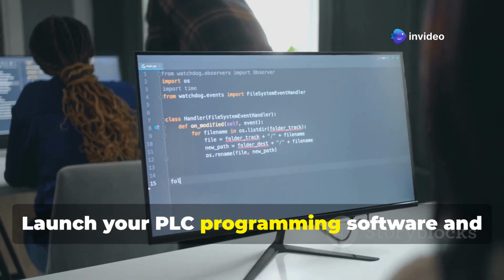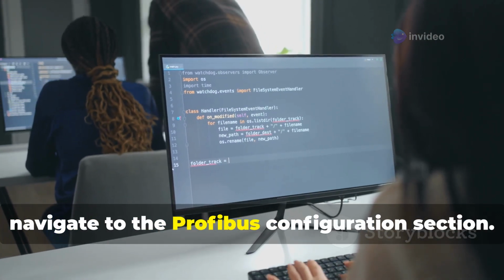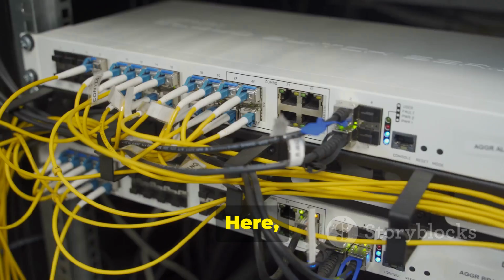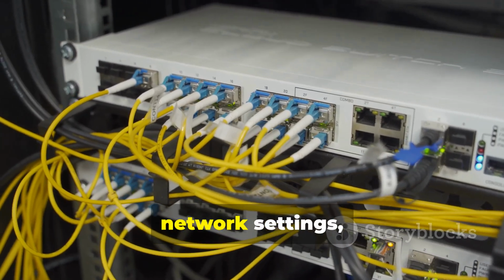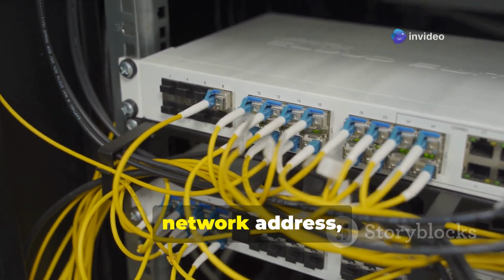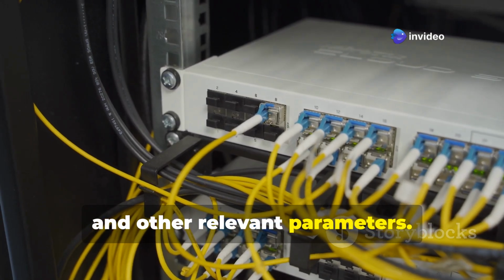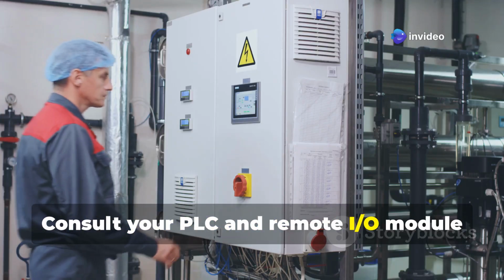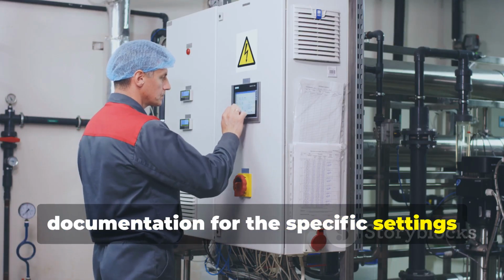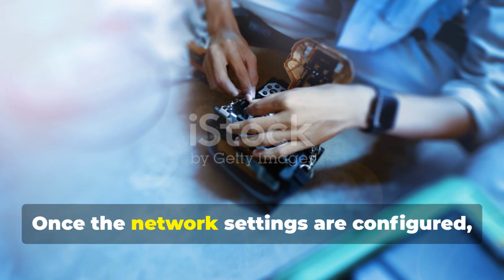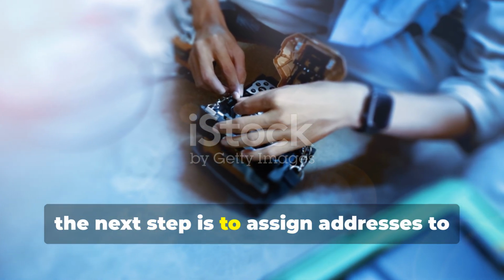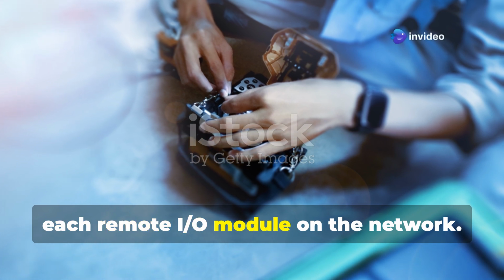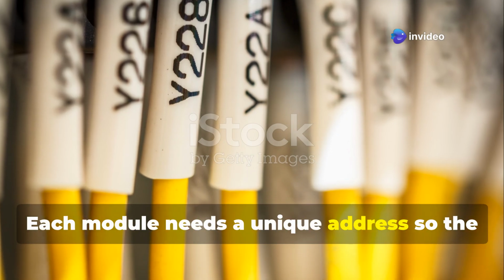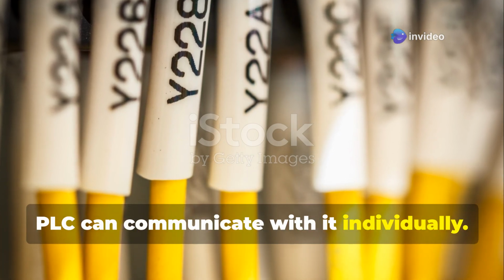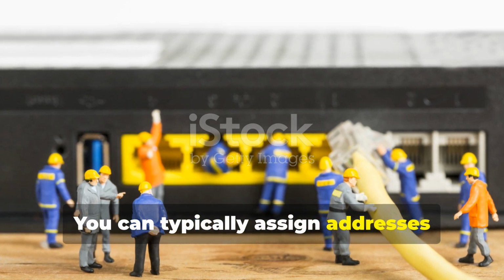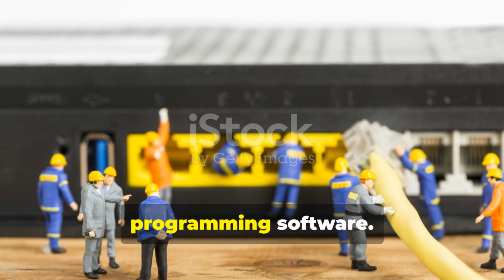Launch your PLC programming software and navigate to the Profibus configuration section. Here you will need to configure the Profibus network settings, including the baud rate, network address, and other relevant parameters. Consult your PLC and remote I/O module documentation for the specific settings required for your setup. Once the network settings are configured, the next step is to assign addresses to each remote I/O module on the network. Each module needs a unique address so the PLC can communicate with it individually. You can typically assign addresses automatically or manually within the programming software.